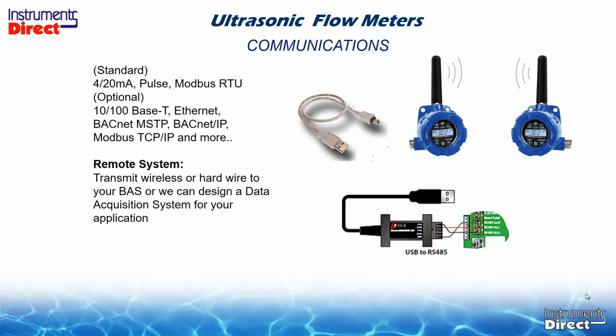Pretty neat, huh? One of the key reasons you need a flow meter is to get the values for some type of control or inventory. So you can just look at the display for flow rate and total and be satisfied. Or if you need to communicate with it remotely, with your control room or building automation system, you may need to consider some of the communication options. If you want to get even fancier, you can tie in a radio system should you need to go wirelessly.